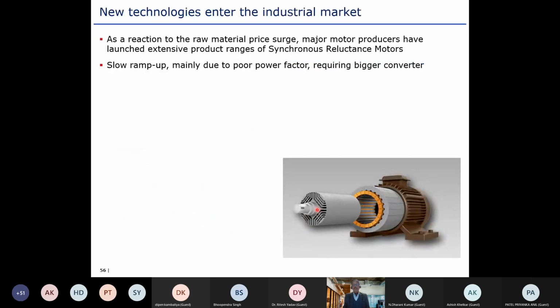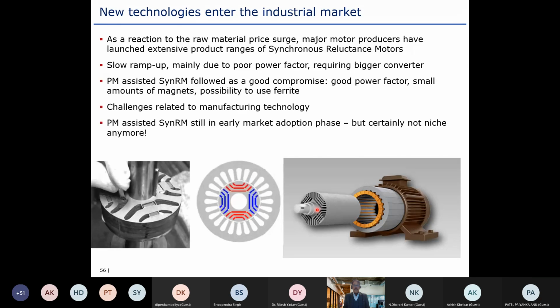So there is a slow ramp-up, mainly due to poor power factor for the magnetless motor, like the synchronous reluctance motor. An alternative is the PM-assisted synchronous reluctance motor, which has good power factor, a small amount of magnet, and the possibility to use ferrite magnet. But challenges related to manufacturing technology remain, and this motor is still in early market adoption phase, though certainly not niche anymore, because Danfoss and our competitors are already supporting control for this motor.